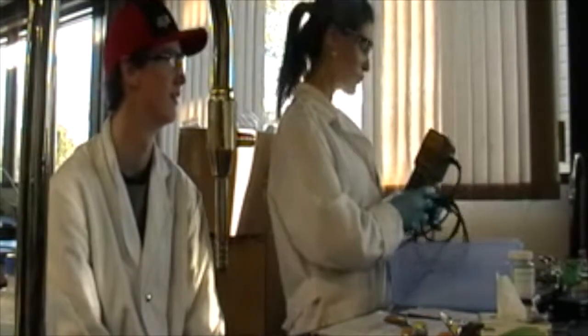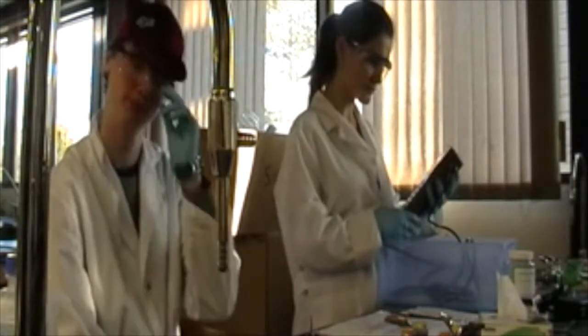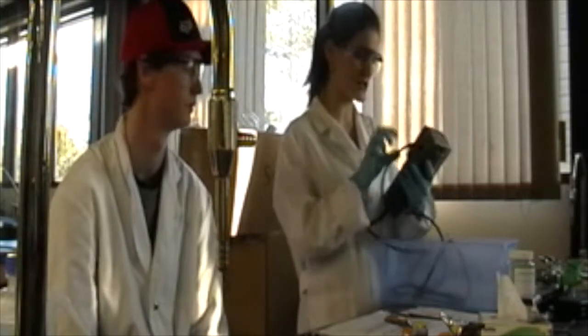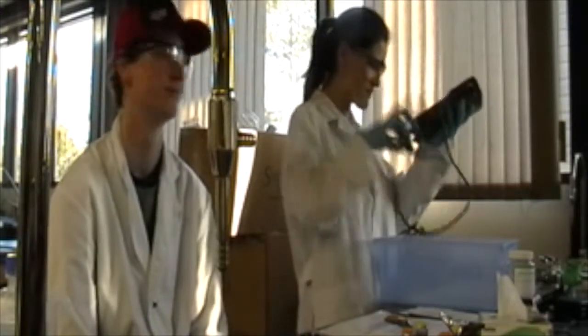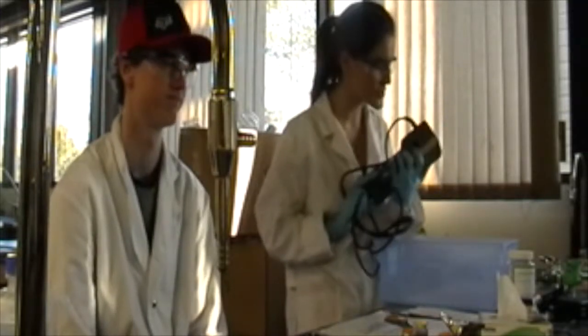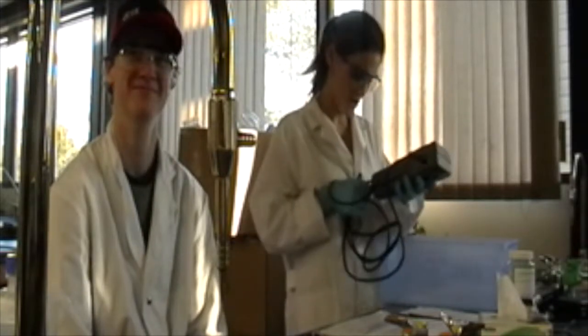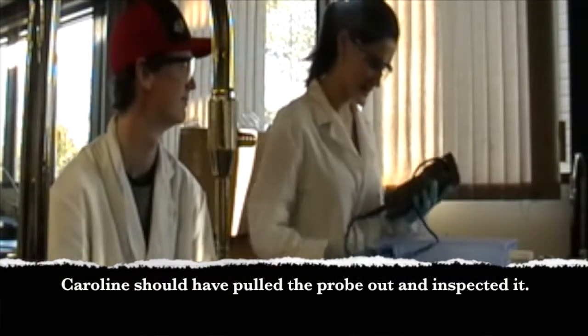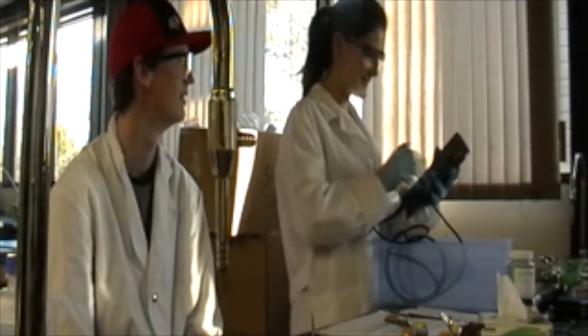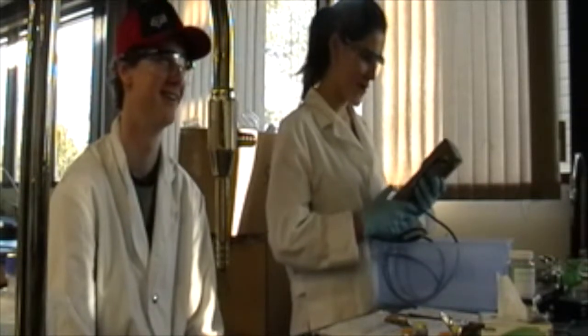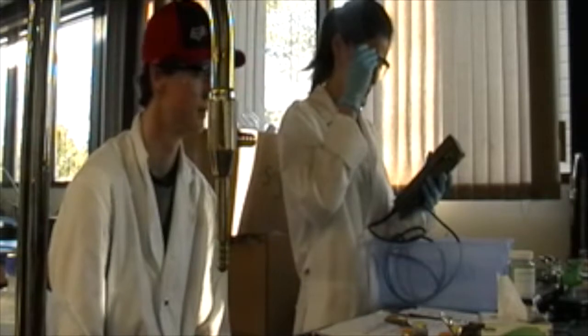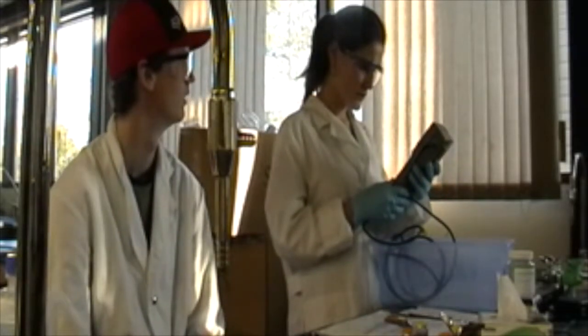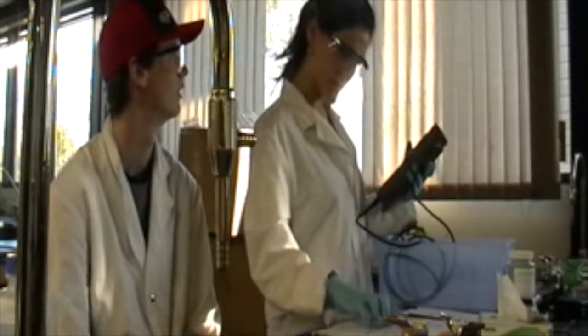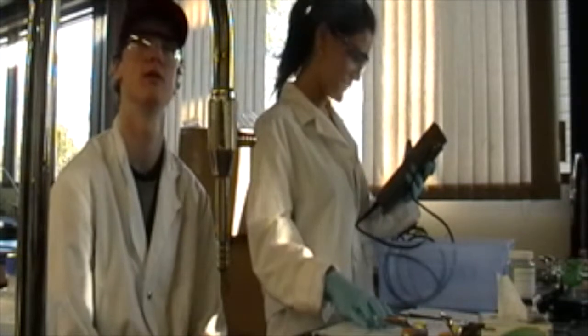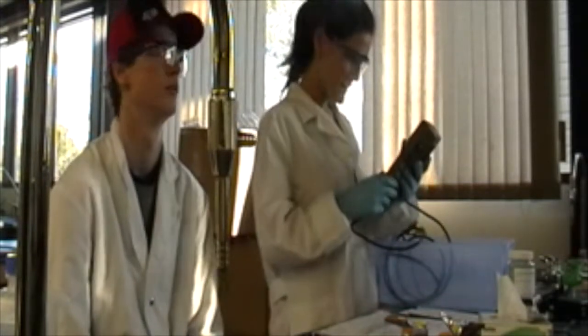So for this test, we're going to be doing the conductivity meter, YSI Model 30. So your first step is to ensure that the electrode and the cable are properly installed. So we're going to do a physical inspection of everything that we've got here before we even turn the instrument on. Everything looks like it's all in order. Secondly, we will turn it on. And then now we are going to find our specific conductance mode. So, lo and behold, we are already on it. How do you know? We know this because the C is flashing for degrees Celsius, and we are in microsiemens for our units.